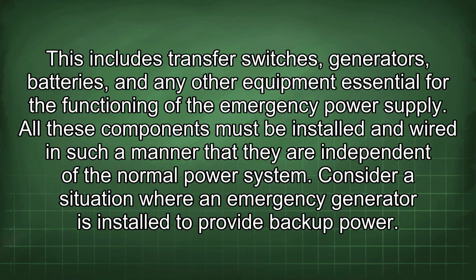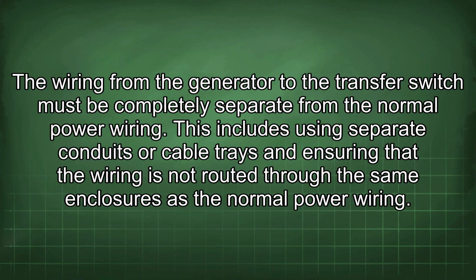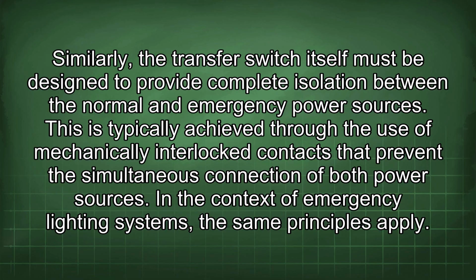All these components must be installed and wired in such a manner that they are independent of the normal power system. Consider a situation where an emergency generator is installed to provide backup power. The wiring from the generator to the transfer switch must be completely separate from the normal power wiring. This includes using separate conduits or cable trays and ensuring that the wiring is not routed through the same enclosures as the normal power wiring. Similarly, the transfer switch itself must be designed to provide complete isolation between the normal and emergency power sources. This is typically achieved through the use of mechanically interlocked contacts that prevent the simultaneous connection of both power sources.